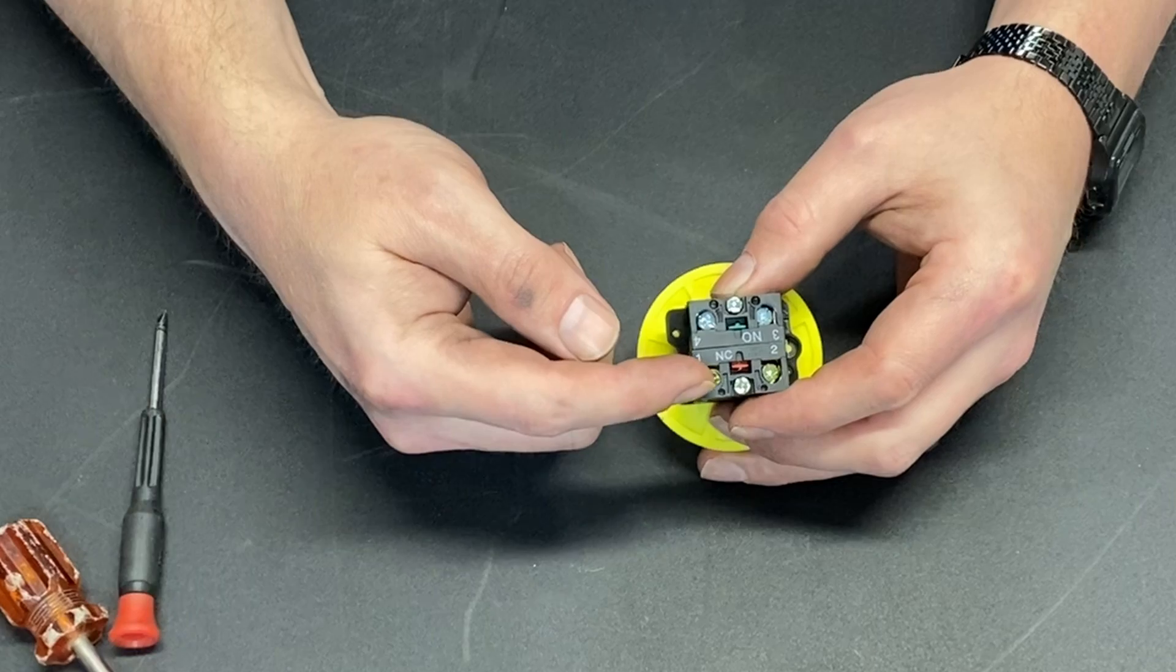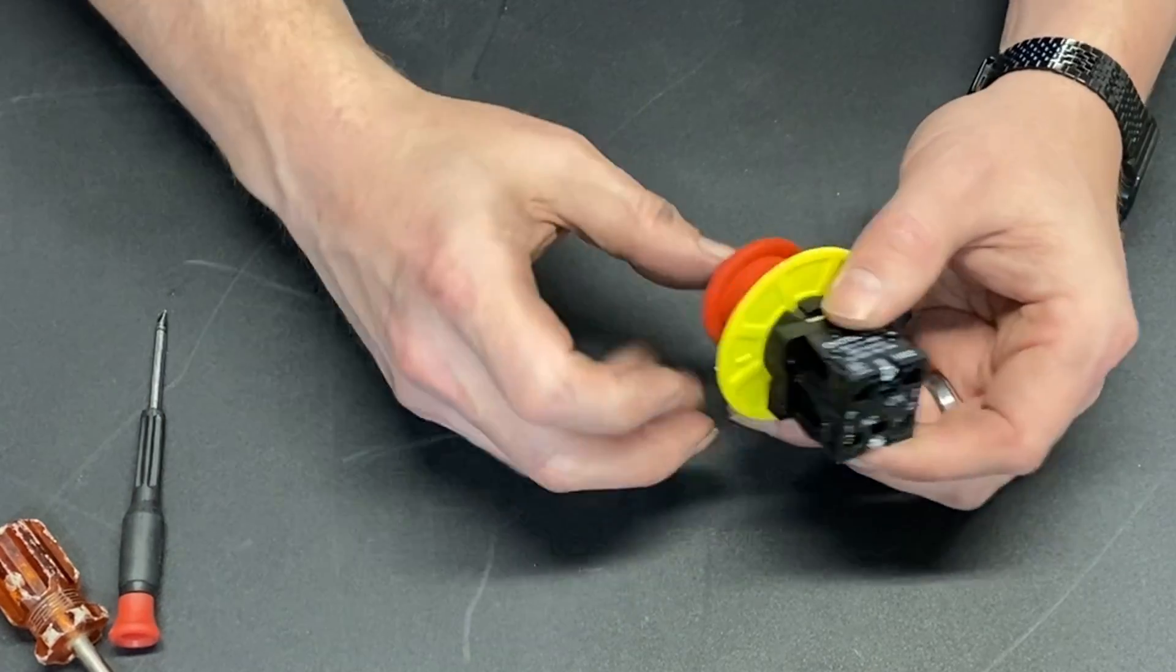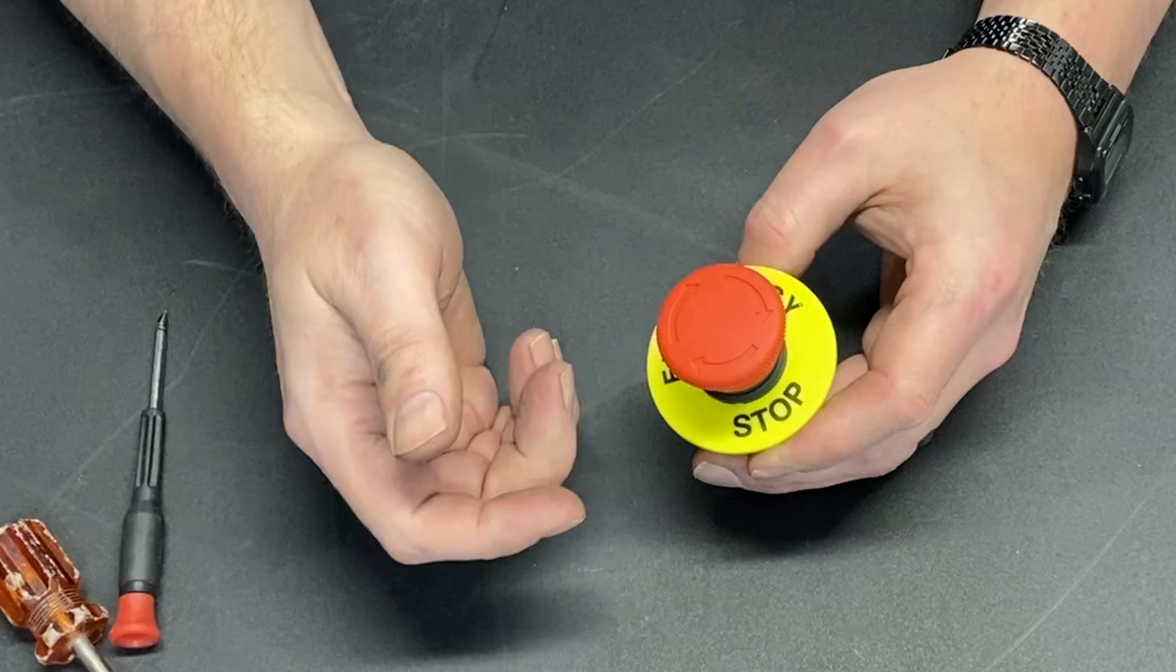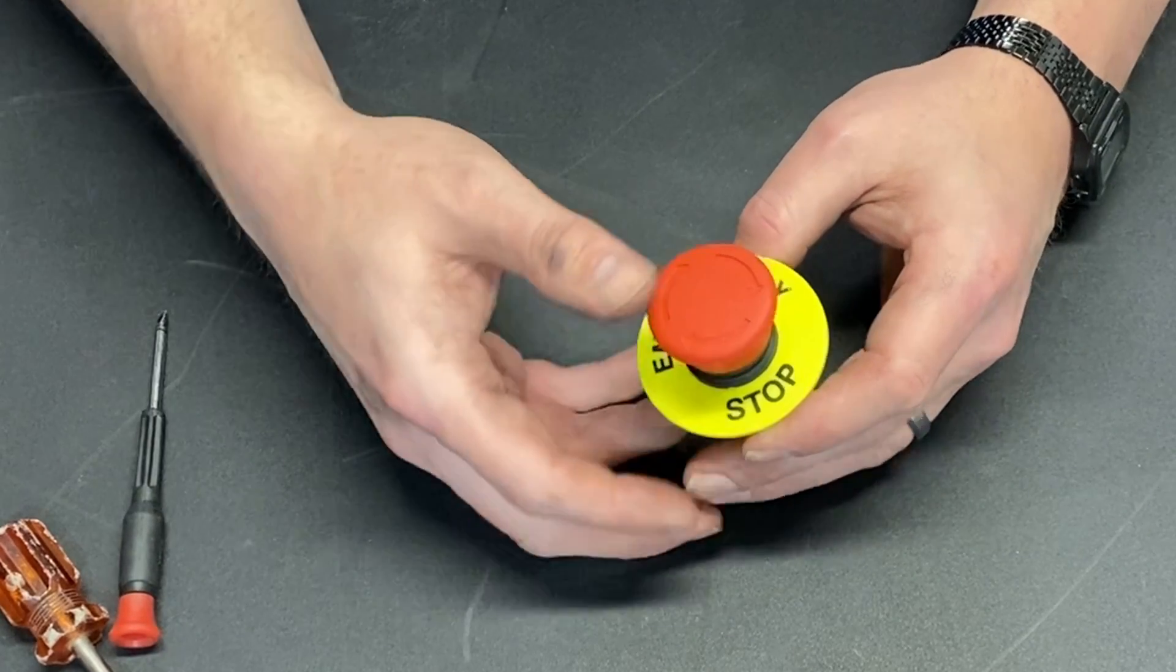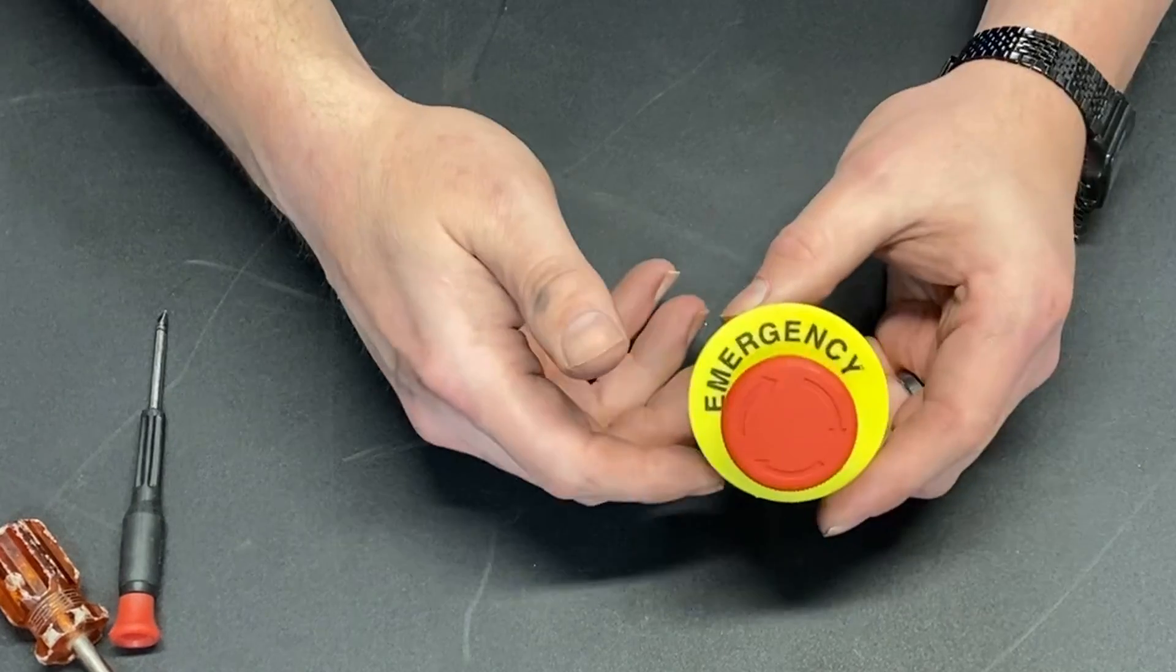The normally closed option would be for your power lead. You would hook it up when we are in the run position, power is flowing, and it works just as it's supposed to. We hit emergency stop, the connection is broken.